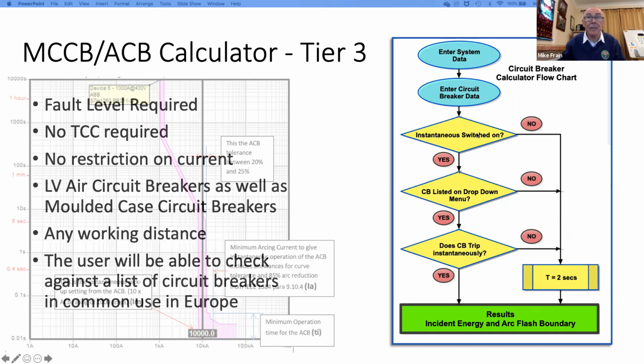And it's just simply after we've put the circuit breaker detail in, but I'm thinking here about system data, 400 volts, like the previous example, or wherever it might be. We look at the circuit breaker. Is the instantaneous switched on? If it is, then is it listed on the drop-down menu? If it is, yes, we go on to the next one. Does a circuit breaker trip instantaneously? You don't have to answer that. The calculator does. And the results are there, the incident energy level for that particular circuit breaker acting instantaneously.